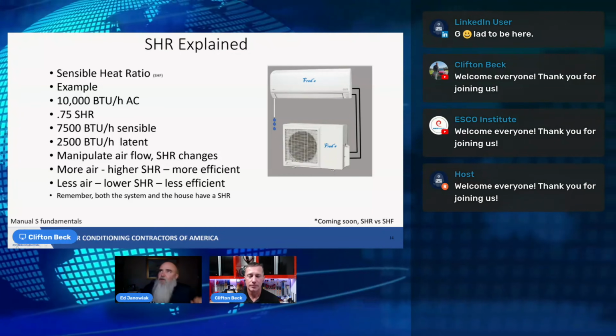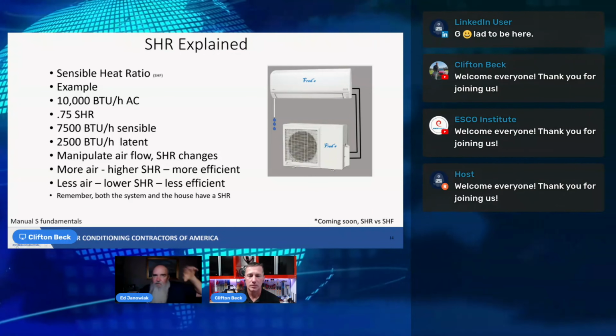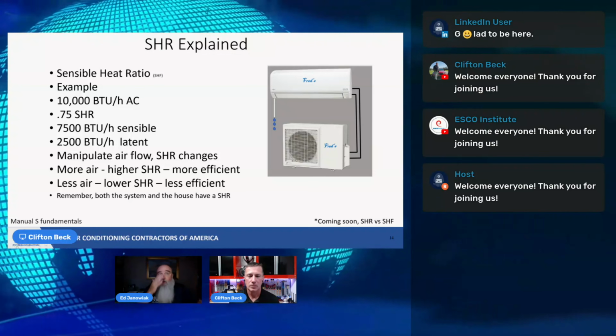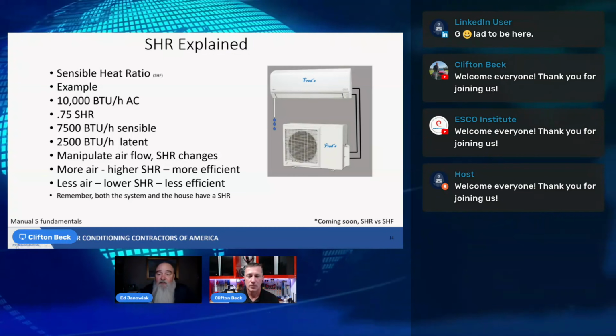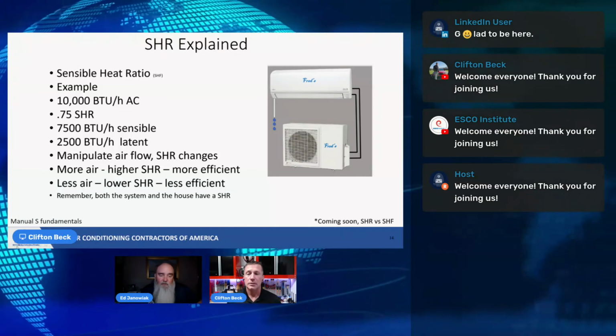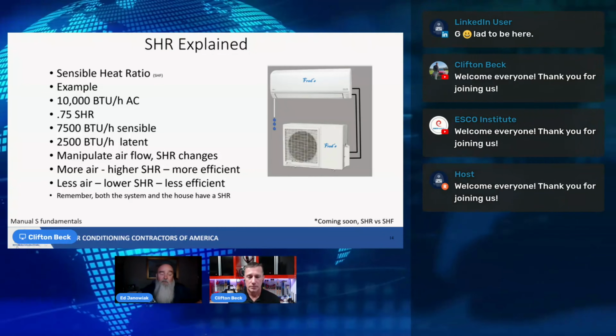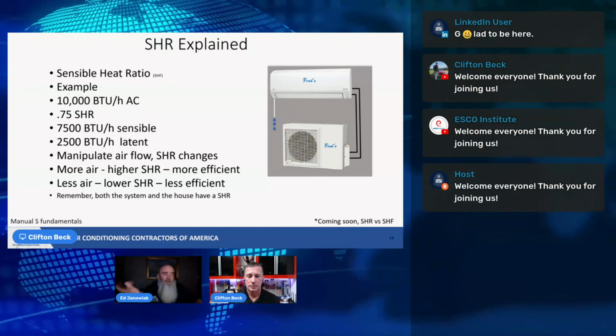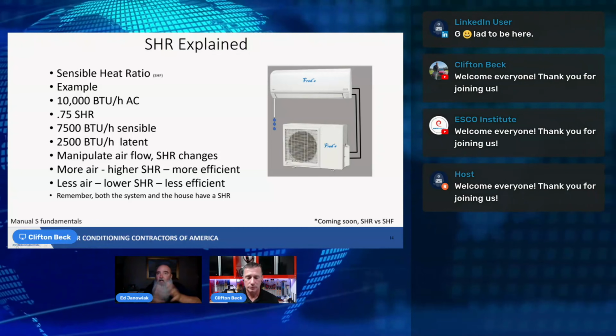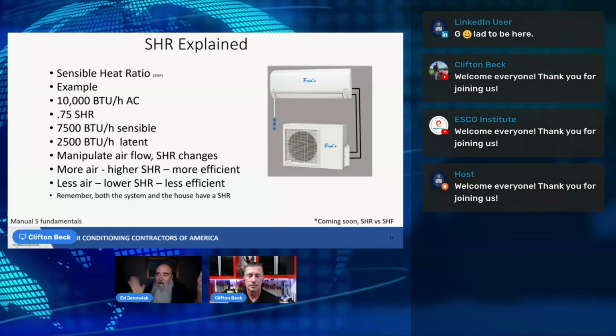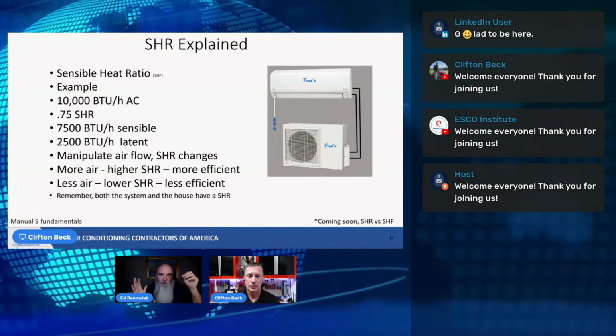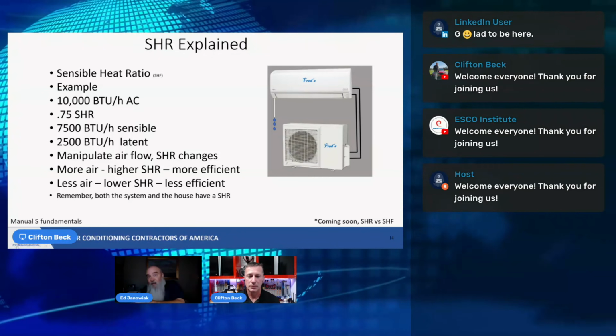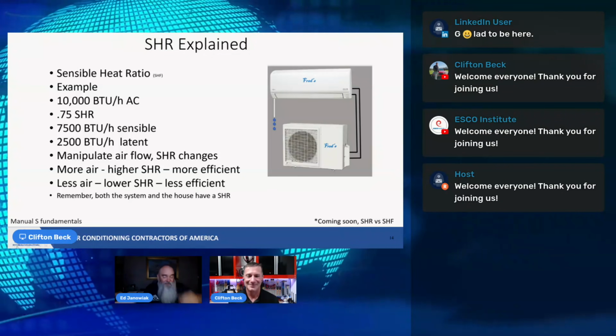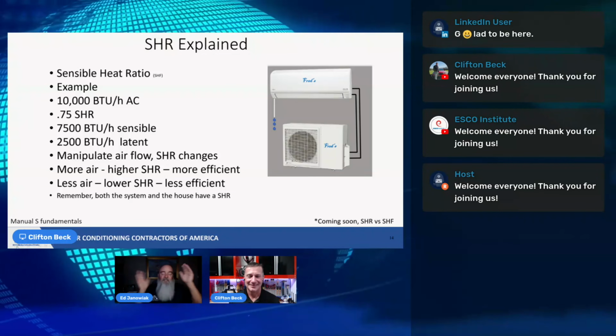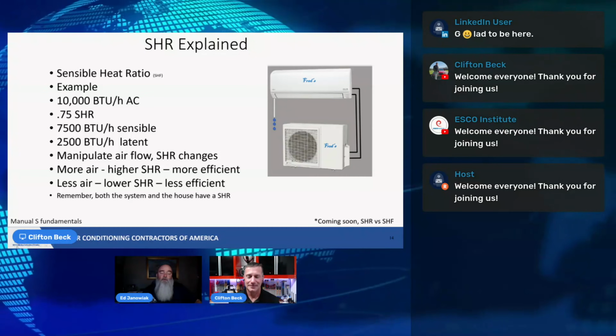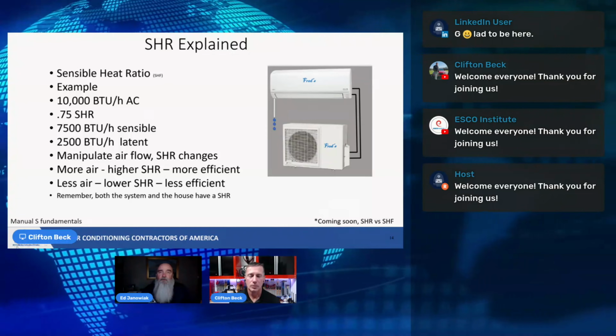Okay. I believe one of the mini split manufacturers already started publishing sensible heat factor, and they were involved. Oh, it was Kimberly who I believe brought it up, and she said we should do this in Manual S for less confusion. Coincide with it. Sure. It's going to be 20 years before I'll be able to stop saying sensible heat ratio for equipment instead of sensible heat factor, but it's a good move to start moving in that direction to make separation between the two terms.